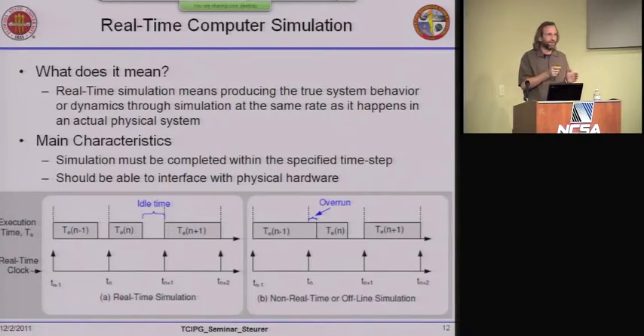This means some of the algorithms used in non-real-time simulations, such as iterative ones, are no good for real-time simulation. You have to acknowledge that you have to finish the one time-step evaluation of the entire system, all the equations governing it, within that 50 microseconds or whatever your scan time is.